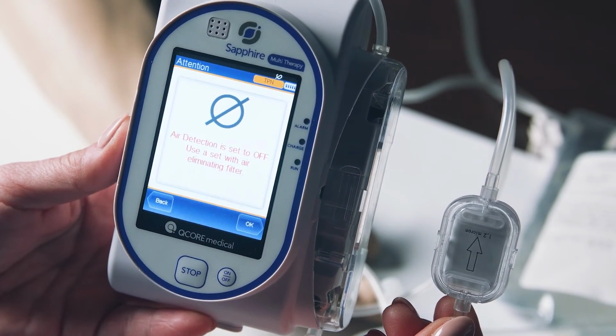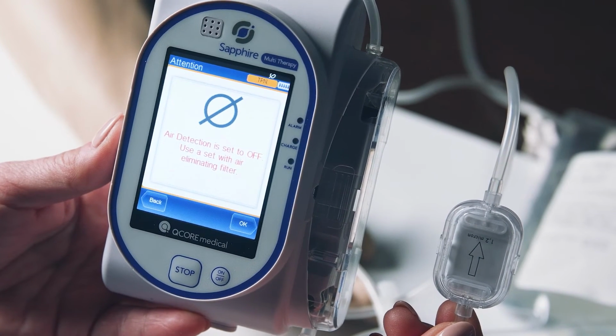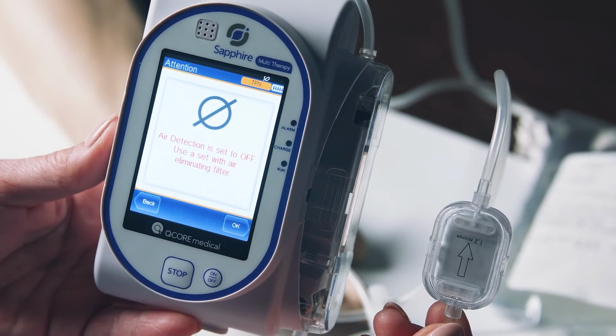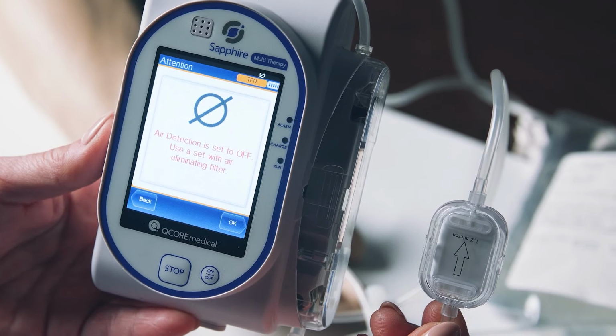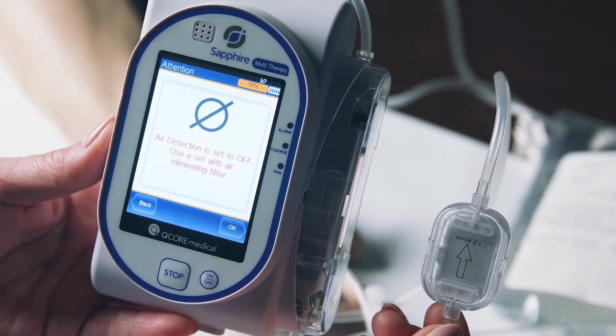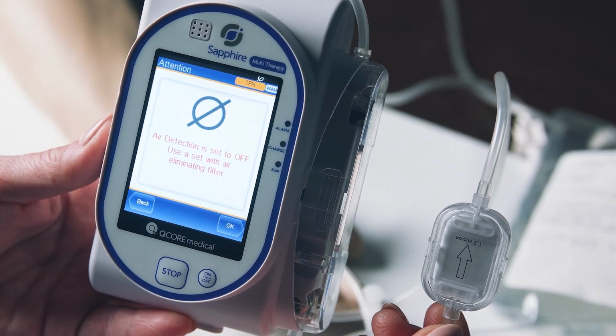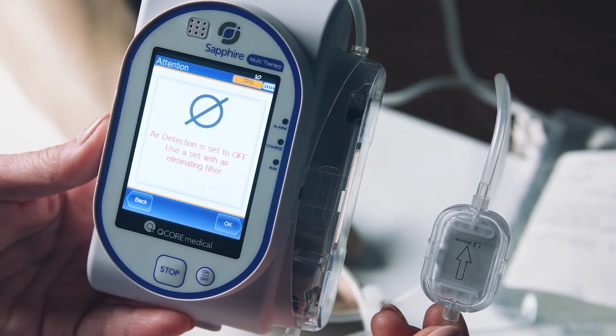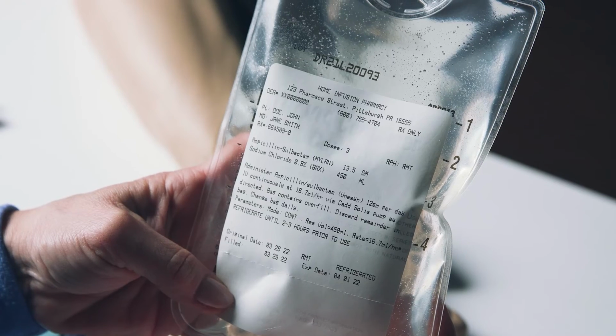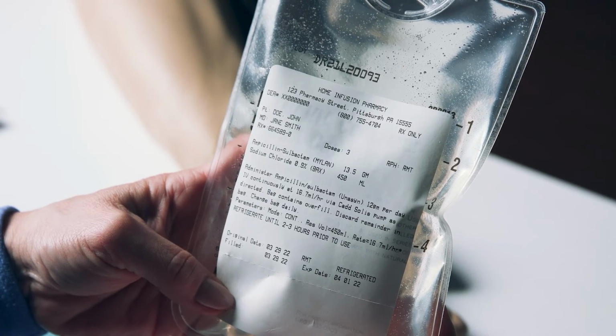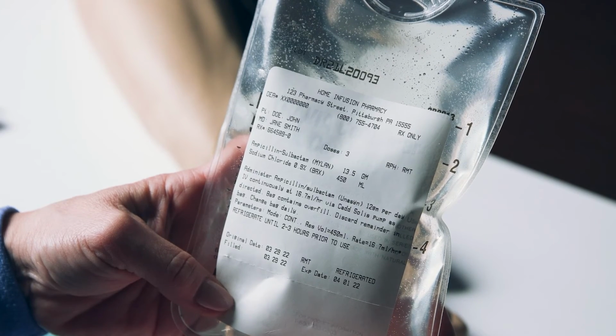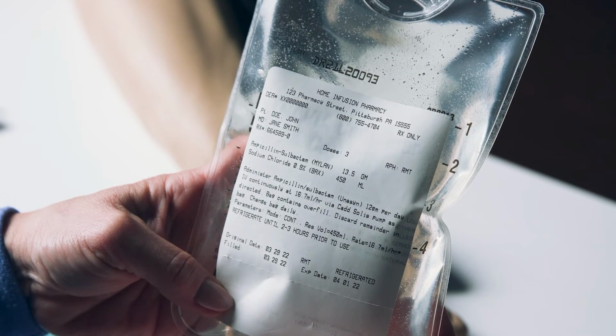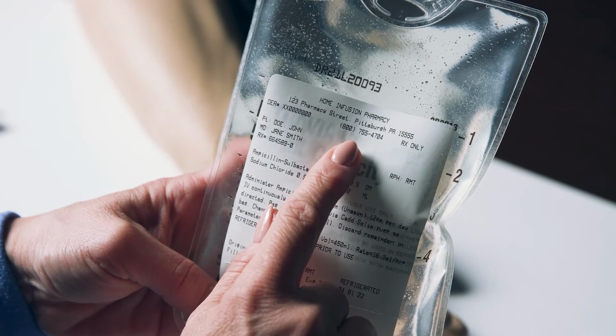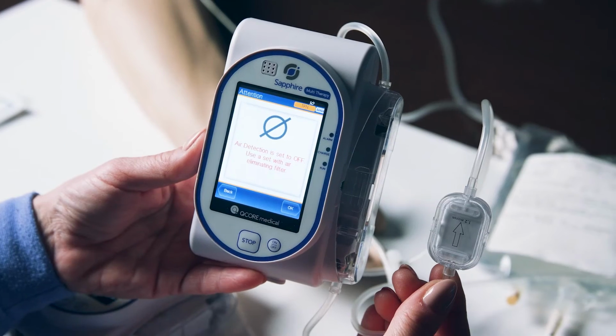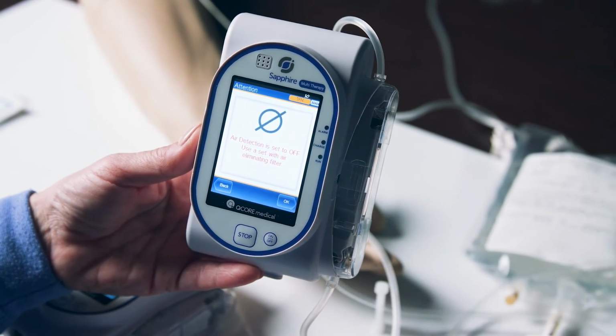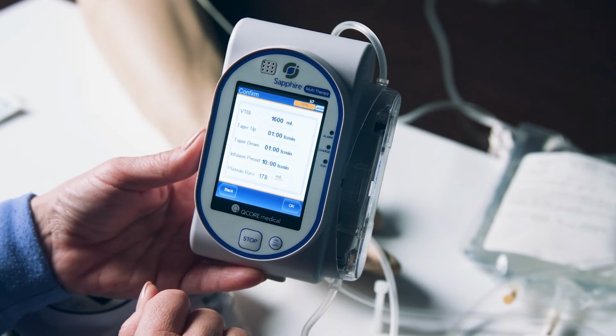You must verify your tubing has an inline filter. All Sapphire inline filters like this one are air eliminating and will not allow air to pass through the filter to your IV catheter. If your pump has this alert and your tubing does not have an inline filter, do not start your medication dose and call your pharmacy at the number listed on the top of your medication prescription label. Once you have confirmed your tubing has an inline filter, press OK.